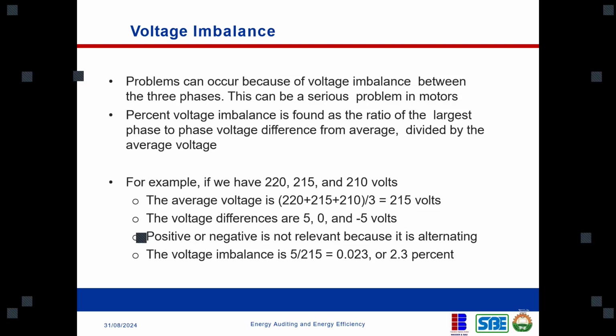The voltage differences are 220 minus 215, which is 5. For the second phase, 215 minus 215, which is 0. And for the third phase, 210 minus 215, which is minus 5. Now, the negative is not relevant here. Whether positive or negative, it is not relevant, because remember, these are alternating current. So it is non-relevant. Now, the voltage imbalance will be the one with the highest deviation, and the highest deviation here is 5.